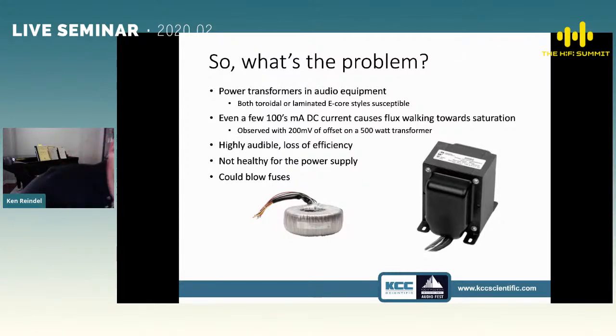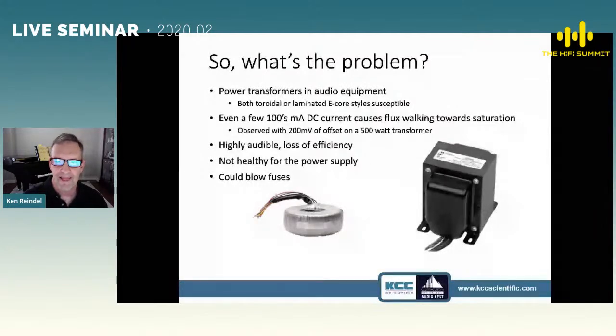Well, it turns out that both toroidal and laminated E-core style transformers hate DC—they absolutely hate it. Even a few hundred milliamps of DC current causes the magnetic flux in the core to walk off into saturation. You will hear it like you wouldn't believe, and not only is it audible, it's not healthy for the power supply, and it could blow fuses. I actually have a demonstration of this very effect.